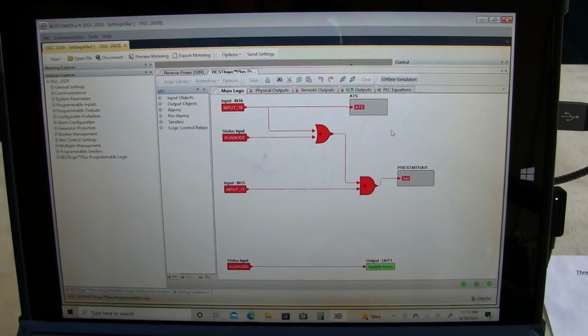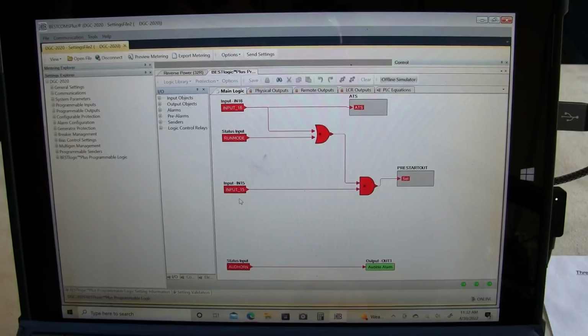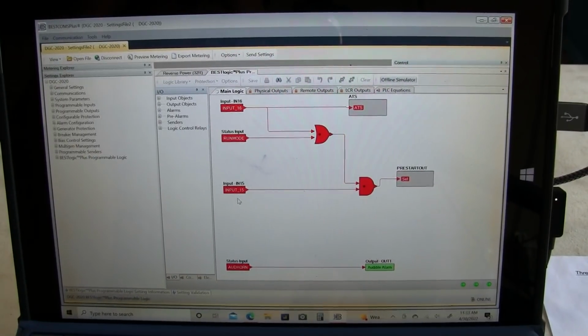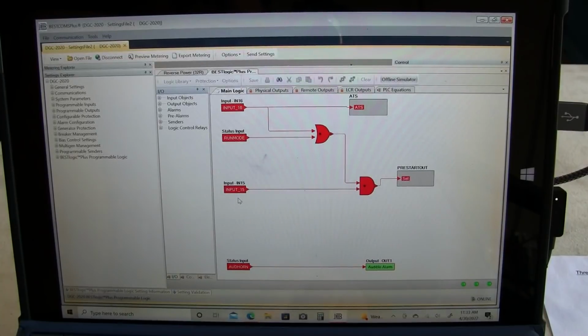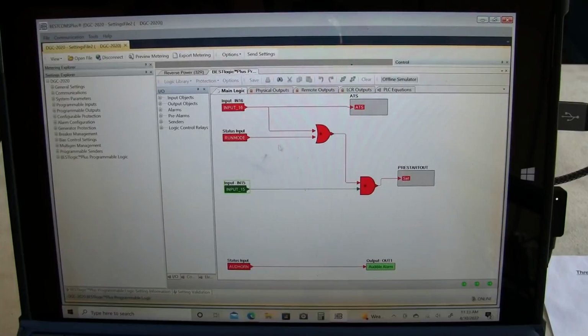Click that. There we go. So let's say we want the preheat to operate. So the thing's not on a block heater, it's cold. If it receives a start signal, we want the little preheater to come on in the intake manifold. So you would flip that toggle switch on, which would activate input 15, so we can activate that. And then in that case, if we enter a run mode for whatever reason, that activates the preheat.